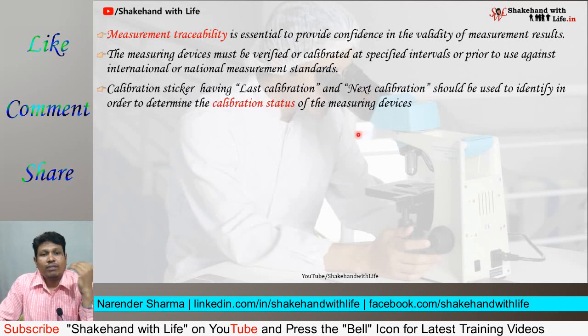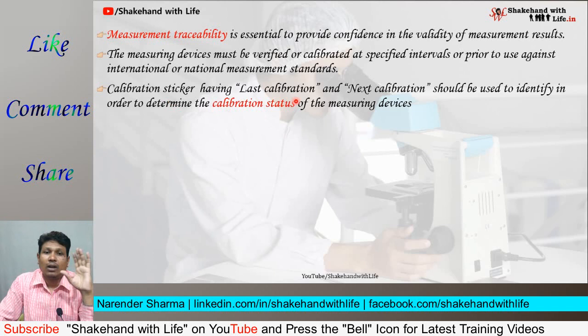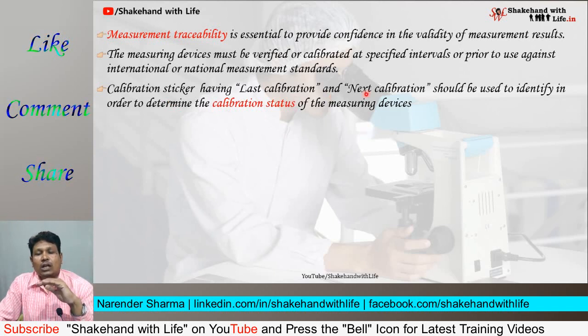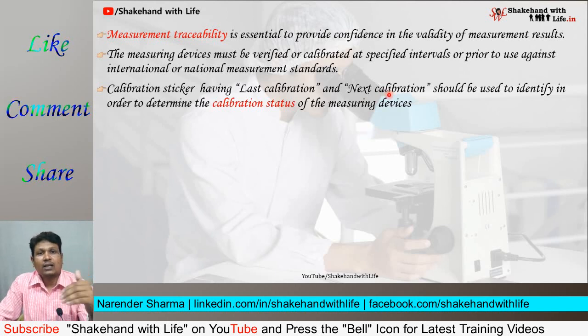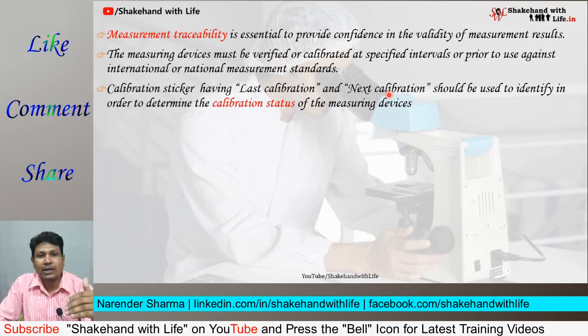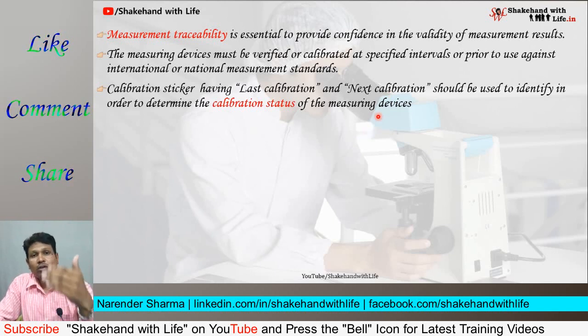For identification of calibration status, a calibration sticker showing the last calibration date and next calibration date should be put on the measuring devices, so that you can identify whether the instrument is calibrated or not, and if calibrated, on which date it was calibrated and on which date it is next due to be calibrated.